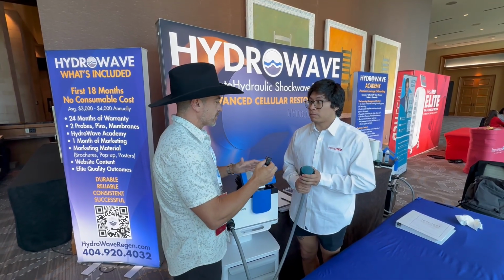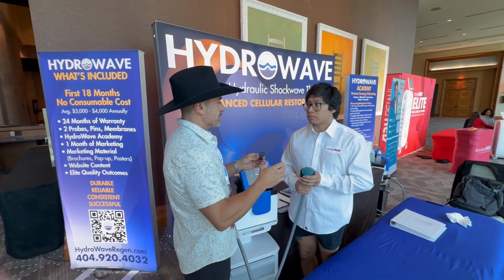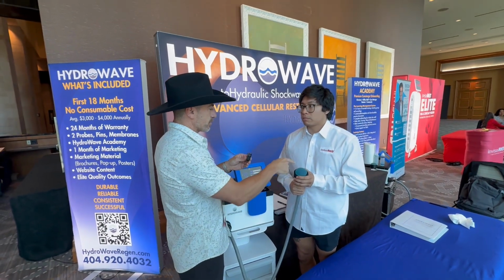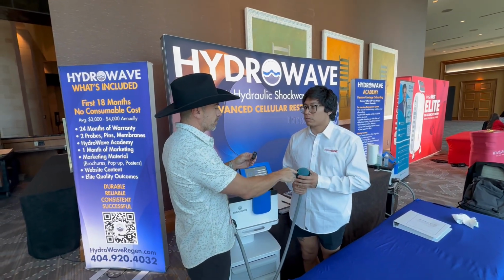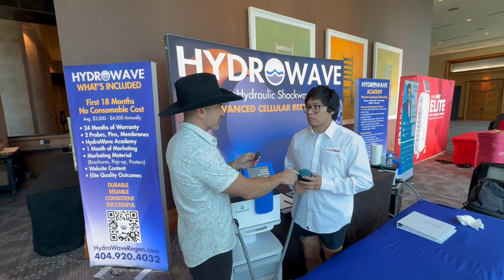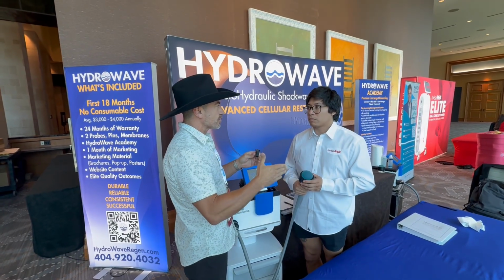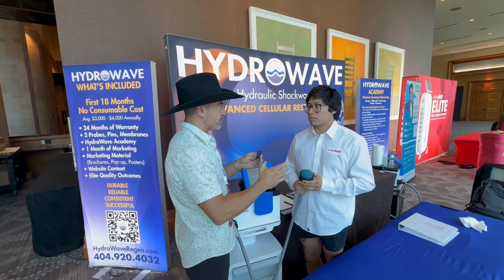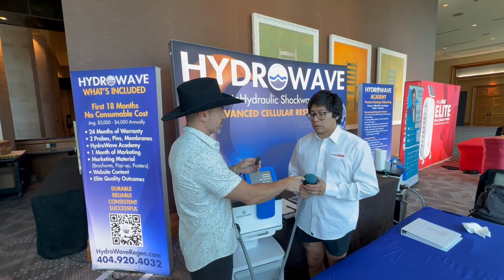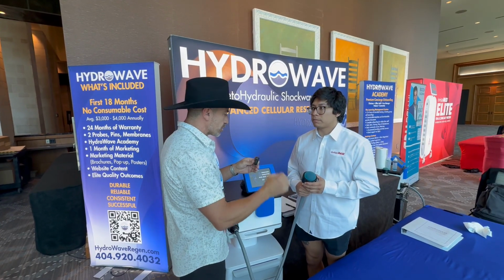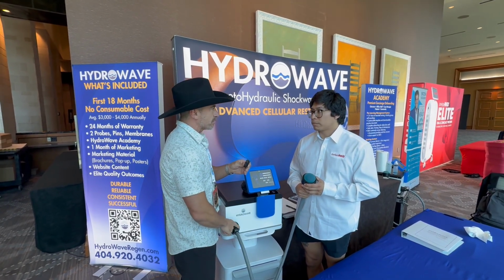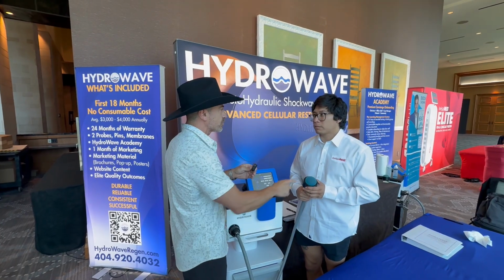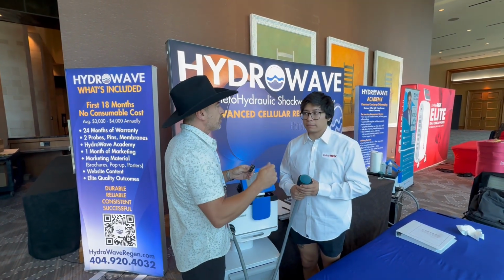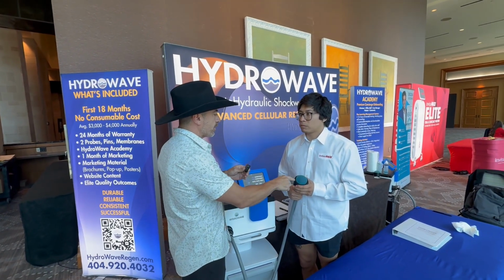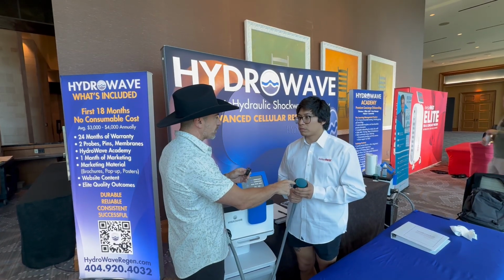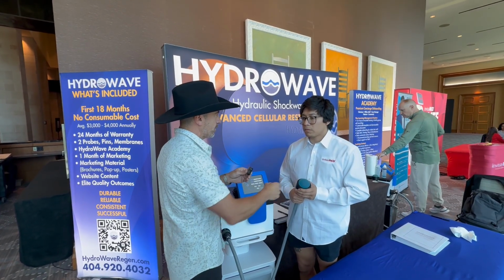Okay, so in other devices, there's going to be a limitation, if I'm understanding this correctly, based on the spark being produced inside the applicator. So that's what causes the erosion. That's what causes the limitation with the amount of shock waves that can be delivered through those applicators. Exactly. It's limited with other devices because the erosion happens there, whereas here you're simply replacing pins versus replacing the entire applicator. Exactly. So my question would be, when, if ever, would I have to replace the actual applicator head?